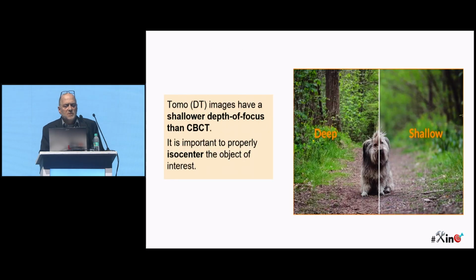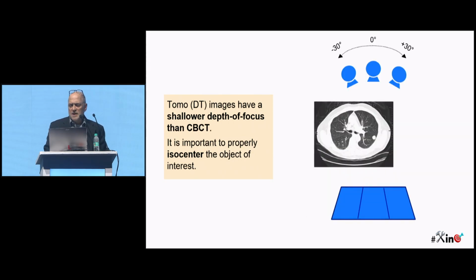The main difference between cone beam CT and digital tomography is the depth of focus. Because you have so much more data, because it's a wider angle spin, you have a much deeper depth of focus in cone beam CT than you would in digital tomography. In digital tomography, the only thing that's clear is the center of that spin, which we call the isocenter. So you don't get depth, you only get shallow. So it becomes very, very important to make sure that when you do these spins, you're at isocenter.